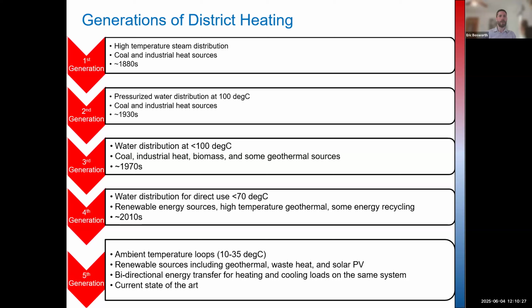It's gotten even lower now, and with fifth generation, what are called ambient temperature loops, we're looking at probably 35 degrees minimum in the winter, and maybe 75 to 80 degrees maximum in the summer. The real innovation there is that you can both heat and cool with that temperature range.